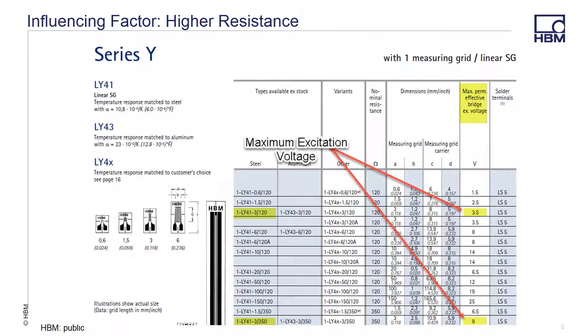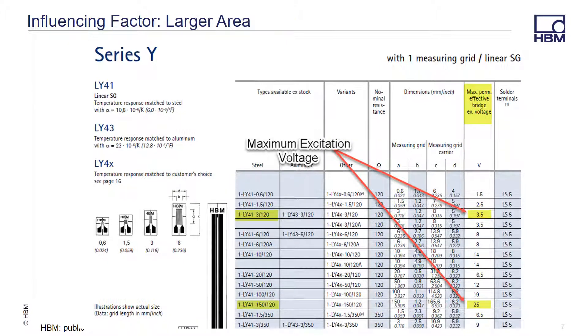Gauges with the same physical size can have much different excitation voltages. In this case, both gauges have a grid size of 3 millimeters, but because their resistance is different — 120 ohms versus 350 ohms — the excitation voltage can differ from 3.5 to 9 volts. In the same manner, here we have two gauges with the same resistance of 120 ohms but different grid sizes: 3 millimeters versus 150 millimeters. The larger area in the 150 millimeter grid size allows the excitation voltage to increase from 3.5 volts to 25 volts.